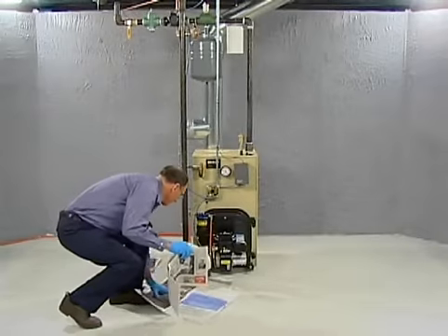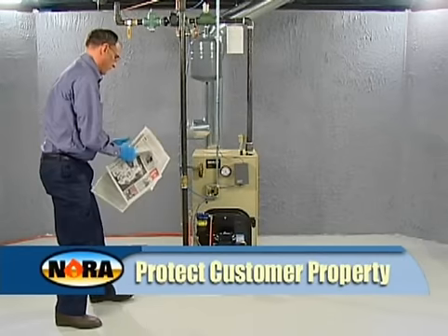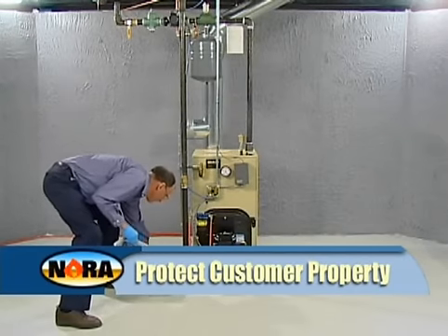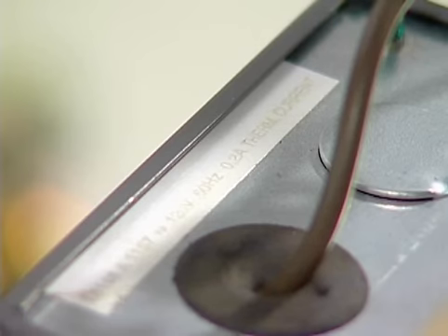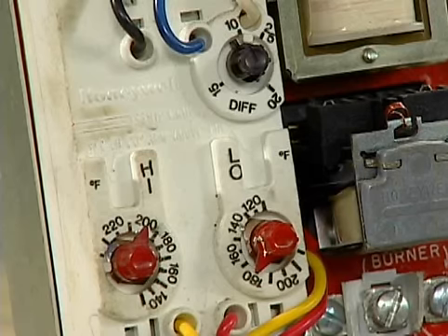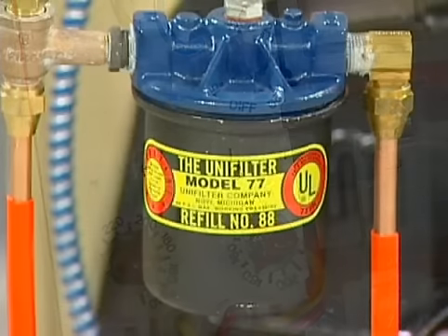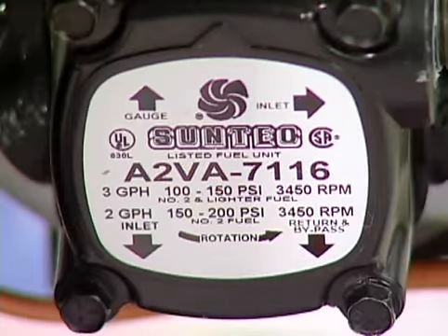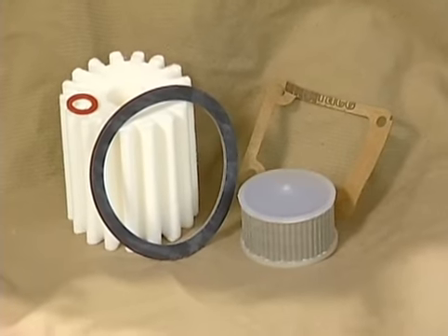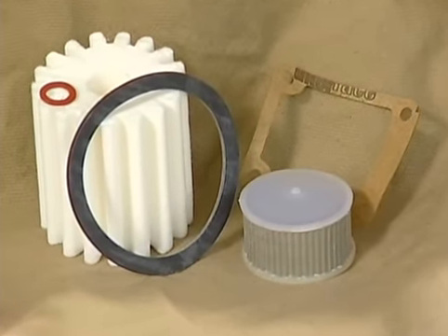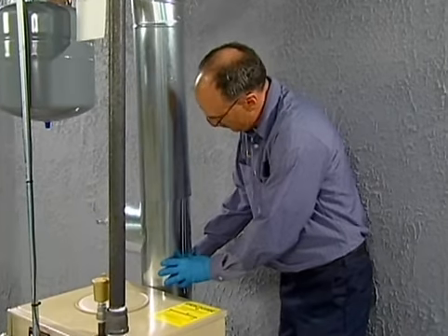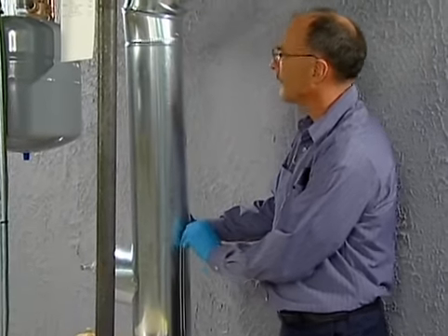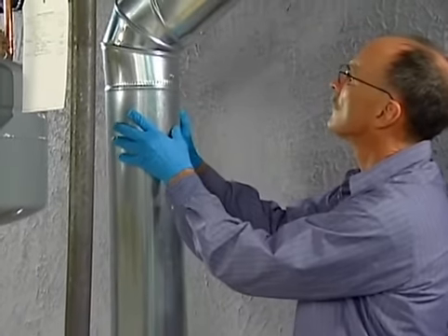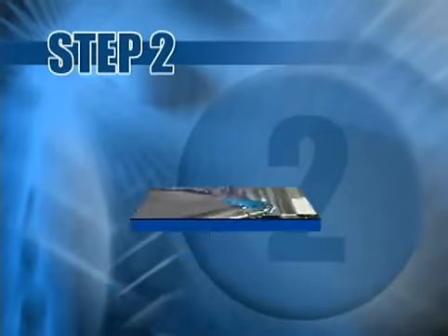Visually inspect the unit and make sure you spread sheets of newspaper or clean drop cloths to protect the work area. Verify the heat anticipator setting marked on the control and that controls are correctly set with the proper differential. Note what kind of filter and pump are installed so you can bring the proper replacement element, strainer, and gaskets. Visually inspect the flue pipe to be sure that it's properly screwed together and supported. If it isn't, add that to your list of things to do.